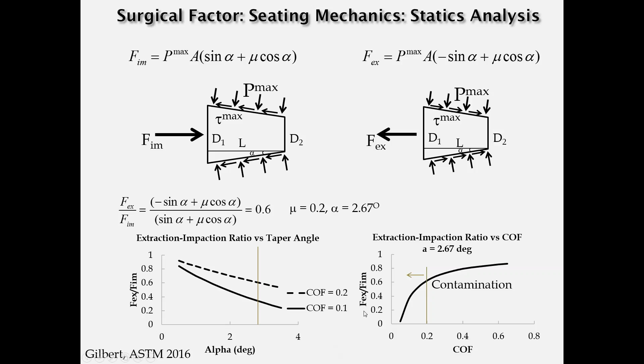And in fact, that ratio of extraction to impaction force is roughly about 0.5 to 0.6 for typical conditions of a modular taper. The graphs I'm showing here show how that ratio of extraction to impaction varies with things like the taper angle as well as the coefficient of friction. And importantly, you can see that when your coefficient of friction of the engagement drops well below 0.2, your ratio falls away quite rapidly. And so if you have contamination or other factors that are reducing the coefficient of friction at that junction, then you can see a loosening of that component relatively easily.